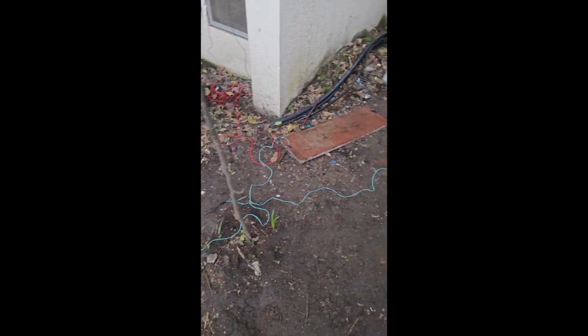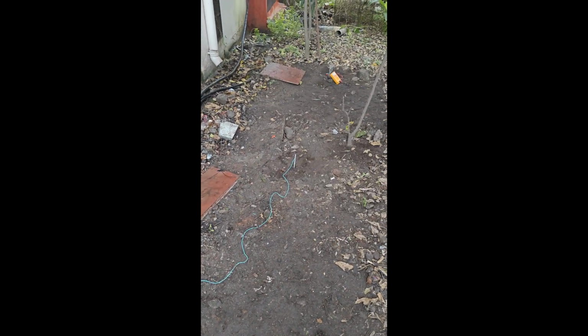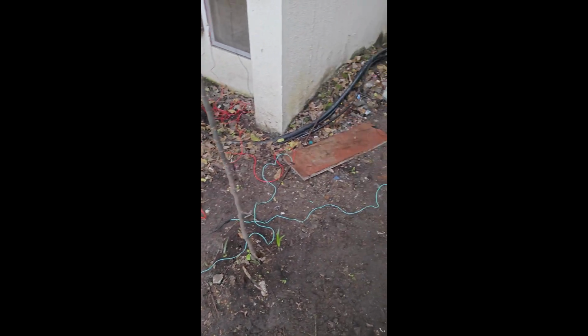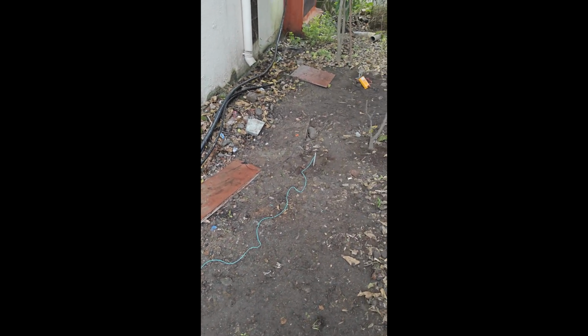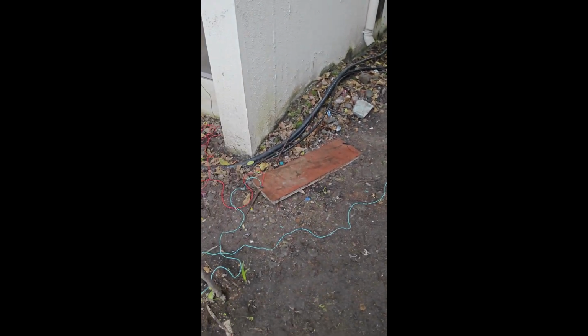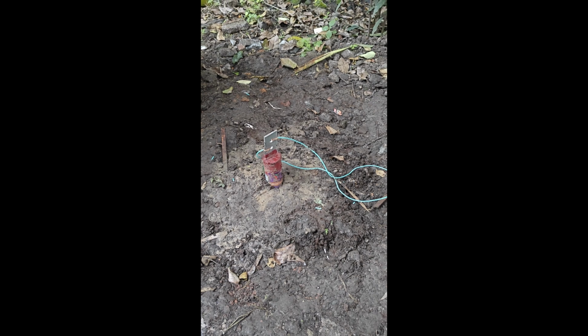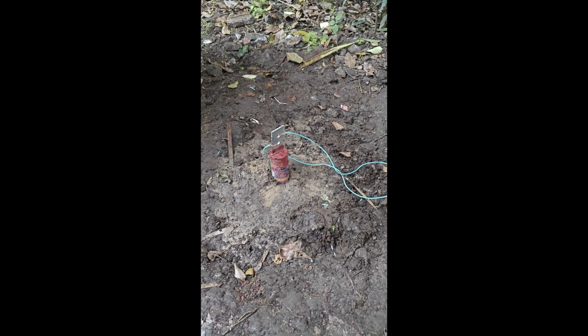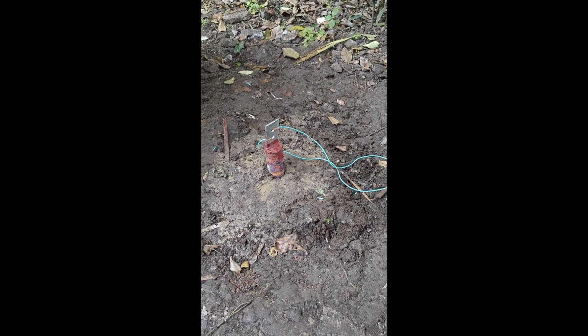By continuously placing this circuit in our earthing system, we continuously measure the earth resistance of our pit, to provide data to our maintenance team. We will also place this earthing rod common between 3 to 4 poles, and this rod will provide earthing to those poles continuously, with earth resistance continuously measured.